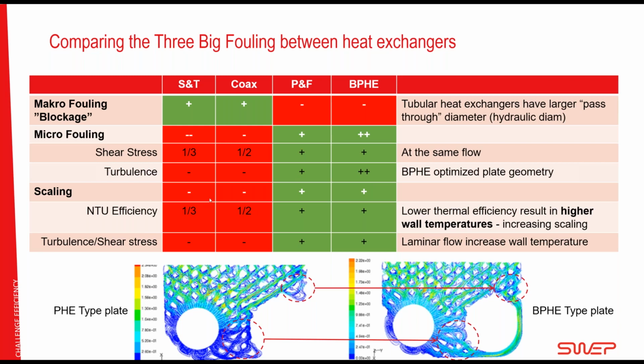When it comes to scaling, again, the shell and tube and coaxials, I rank them below the plate and frame and brazed plate, mainly because for the same surface area, the plate and frame and brazed plate heat exchangers are thermally outperforming the shell and tube and the coaxials. Why is this important? Well, as we discussed before, the wall temperature is very important. I used 140 Fahrenheit as the maximum temperature that we would recommend as a leaving water temperature. But to have 140 Fahrenheit water temperature, the coaxial and shell and tube need to have a wall temperature well above 140 Fahrenheit, whereas a plate and frame and brazed plate can work with a much tighter LMTD due to the increased turbulence and the geometry of the plate type heat exchanger.